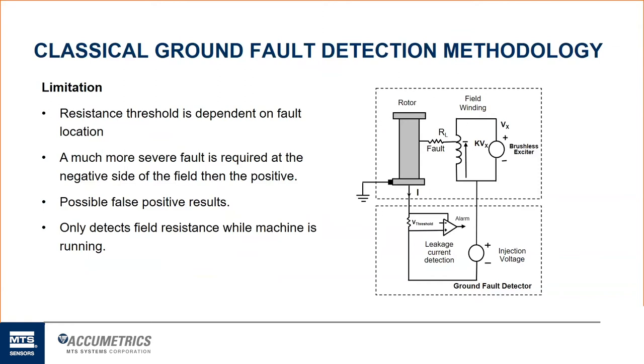So then some of the limitations of the classical method is the resistance threshold is dependent on the fault location. It's also dependent on the severity of the fault. So you would need a much more severe fault near the negative side of the field windings and a relatively minor fault near the positive side. So that could potentially lead to possible false positive ground fault results. We've had customers air their frustration on that where they thought their detector measured a low ground fault and they shut the machine down and did further testing, megger and hipot testing, and discovered that that wasn't the case. It also only detects field resistance while the machine is running. And of course, in most cases, there are those mechanical and physical limitations from either the optical sensor or the brush rigging, slip ring assembly.